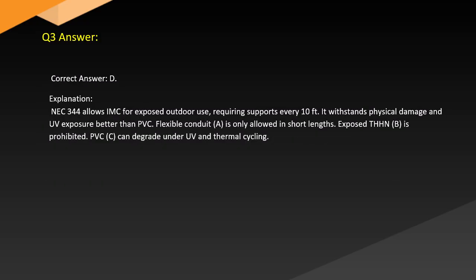Answer. Correct answer: D. Explanation. NEC 344 allows IMC for exposed outdoor use, requiring supports every 10 feet. It withstands physical damage and UV exposure better than PVC. Flexible conduit (A) is only allowed in short lengths. Exposed THHN (B) is prohibited. PVC (C) can degrade under UV and thermal cycling.